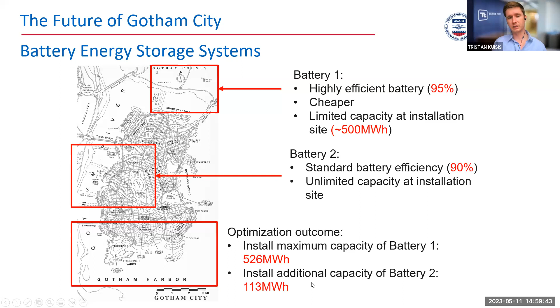So what else did the optimizer tell us? It said install 526 megawatt hours of the first battery, which is very close to our limit. But even with this 526 megawatt hours, it's still not enough to cater for the system. We still need a bit of additional battery energy storage from our second substation. Even though it's more expensive and a little less efficient, it still makes sense to install batteries there - about 113 megawatt hours.